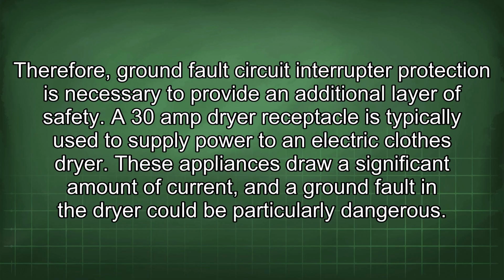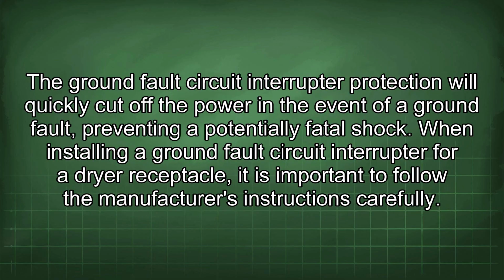A 30 amp dryer receptacle is typically used to supply power to an electric clothes dryer. These appliances draw a significant amount of current, and a ground fault in the dryer could be particularly dangerous. The ground fault circuit interrupter protection will quickly cut off the power in the event of a ground fault, preventing a potentially fatal shock.